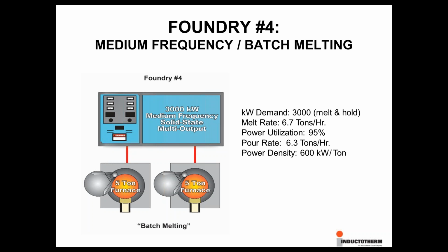Again, medium frequency allows us to increase the power density and reduce the size of the furnaces. This is a batch butterfly operation, whereas one furnace is being melted while the other furnace is either off or at hold for melt preparation and pouring. Once one furnace has completed its melt cycle, the melt process begins on the second furnace, resulting in a very high power supply utilization, up to as high as 95%. As compared to the previous examples, we have reduced the kilowatt demand substantially while still maintaining a similar pour rate.